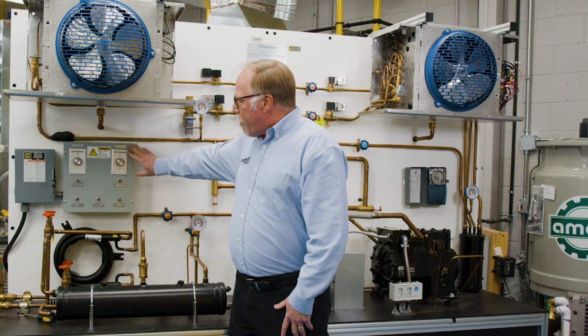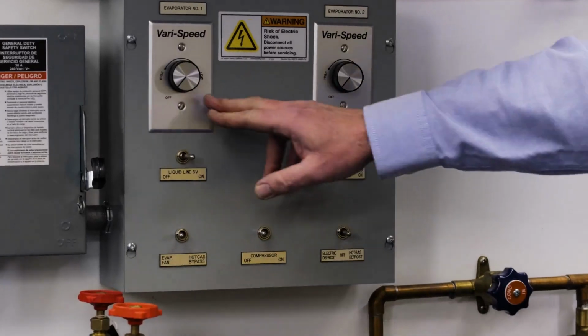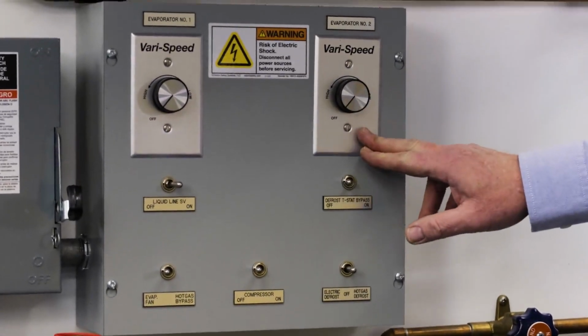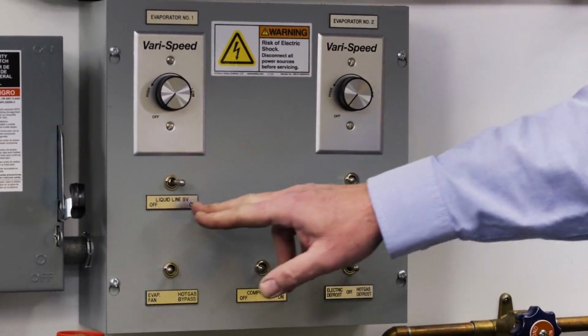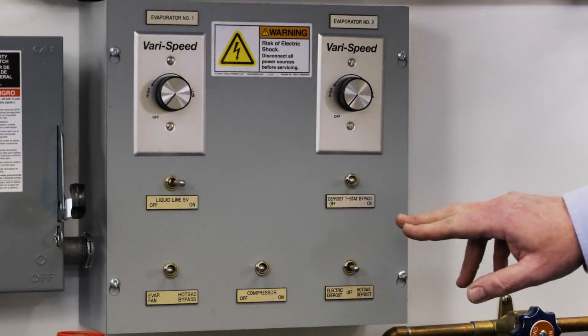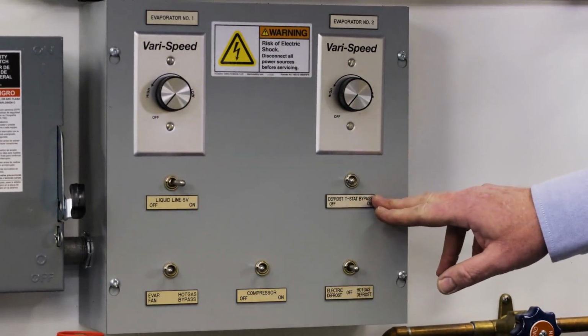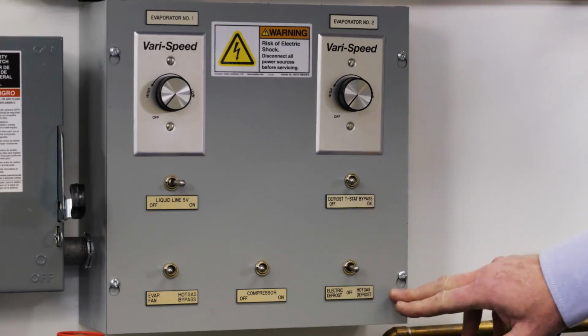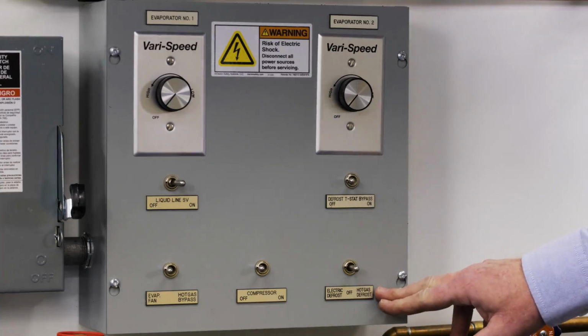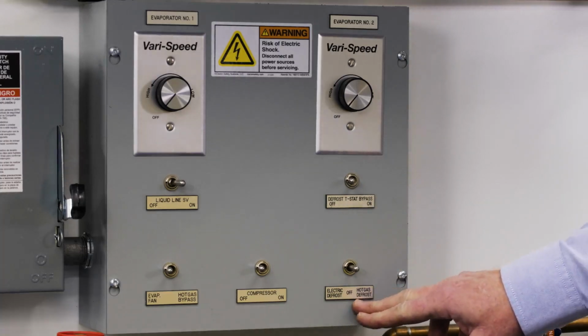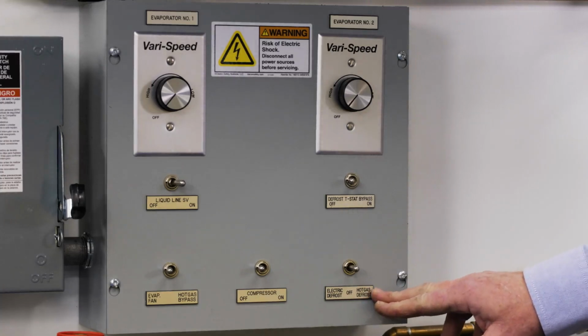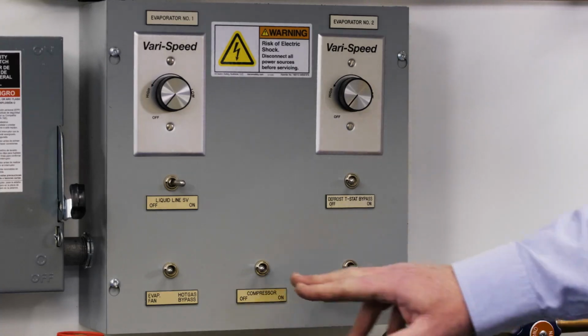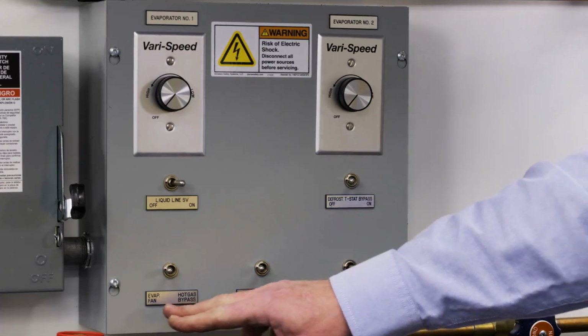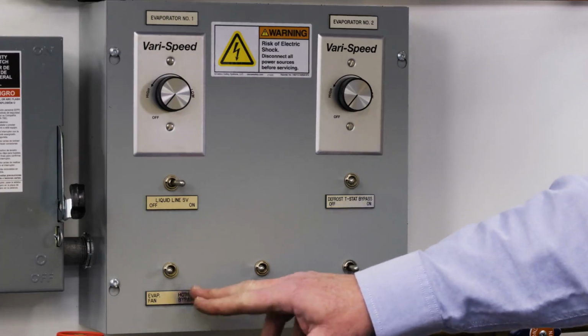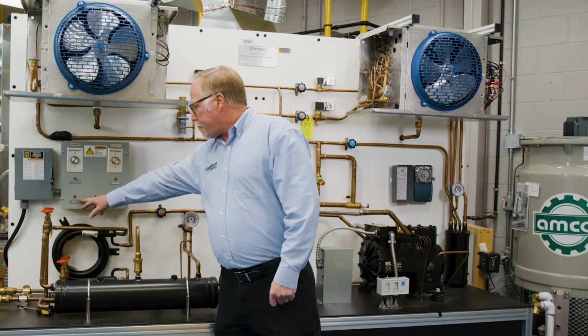Above over here, we have our control center. We can control the speed of each evaporator fan, as well as our liquid line solenoid valve. We can also use our hot gas bypass valve. We have a defrost time clock, which will operate either electric defrost or hot gas bypass defrost. We have our compressor switch here, as well as our evaporator fan and hot gas bypass switch over here.